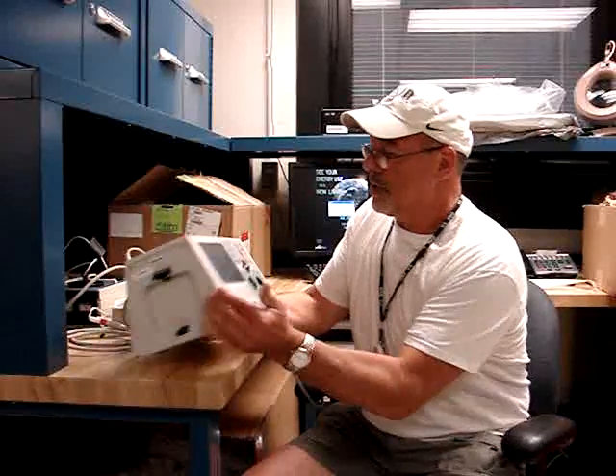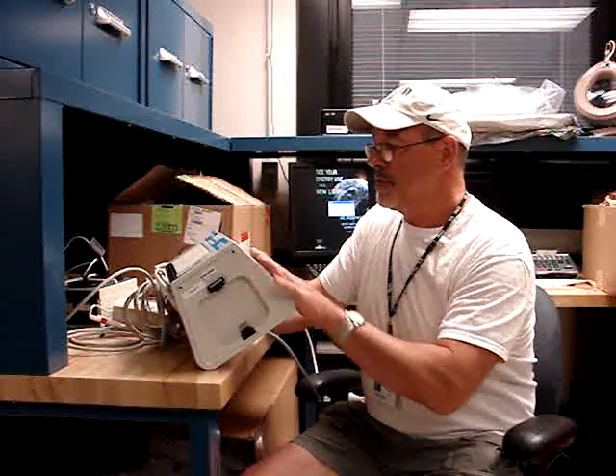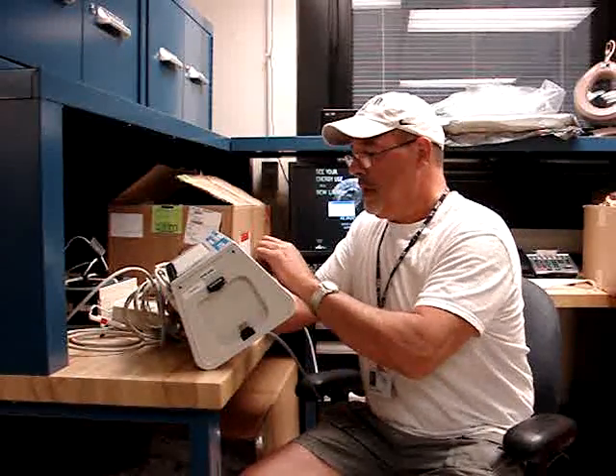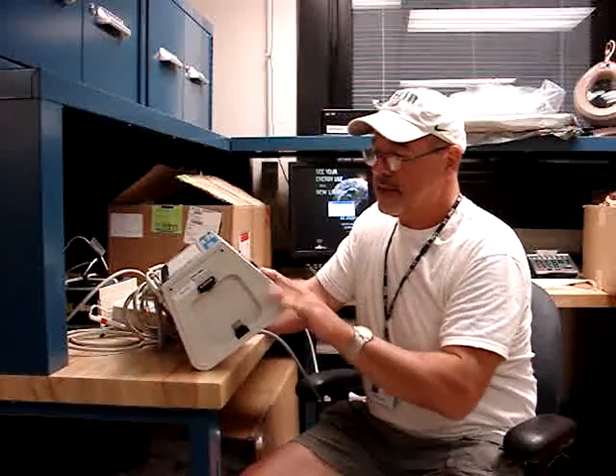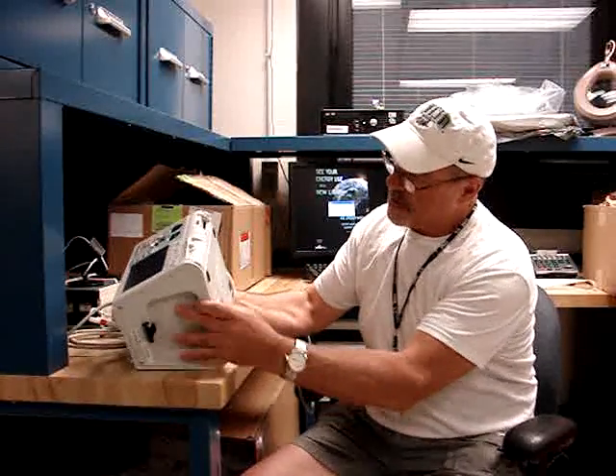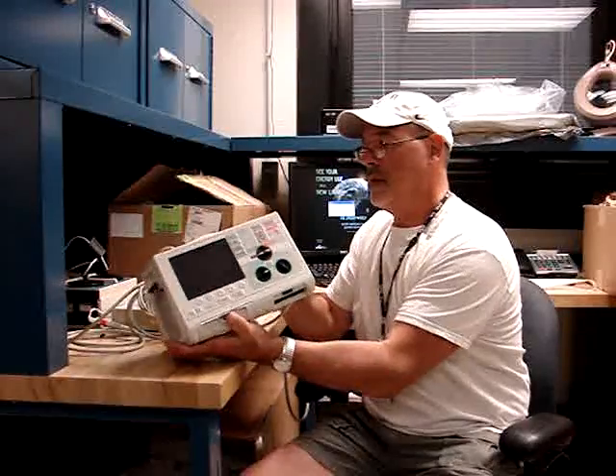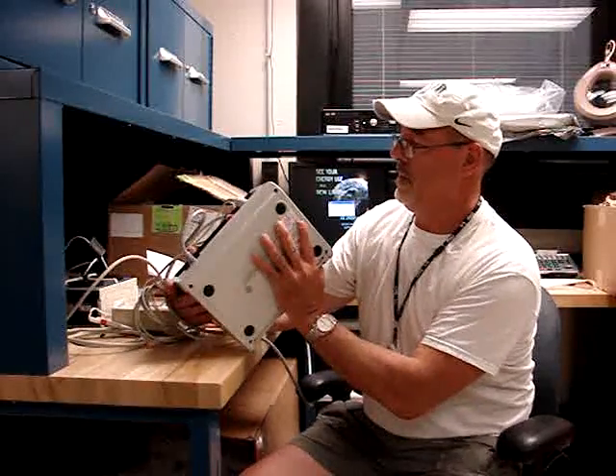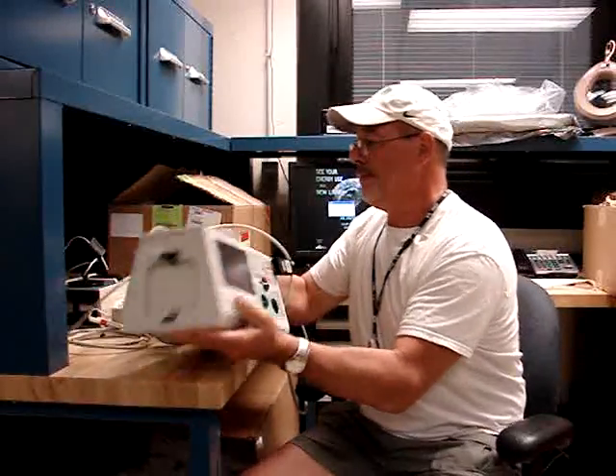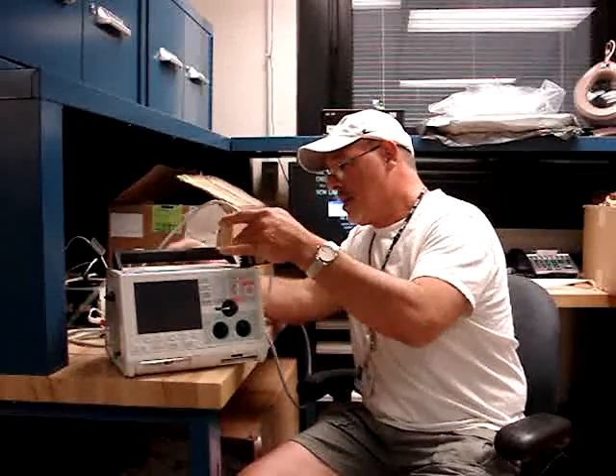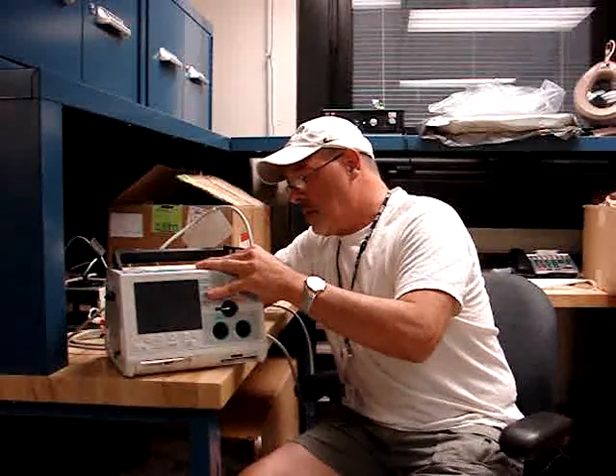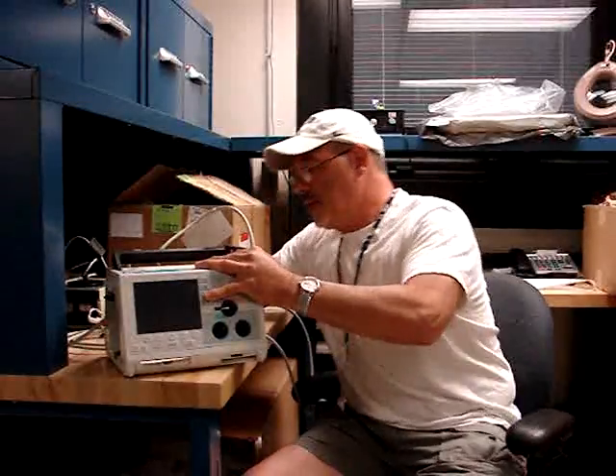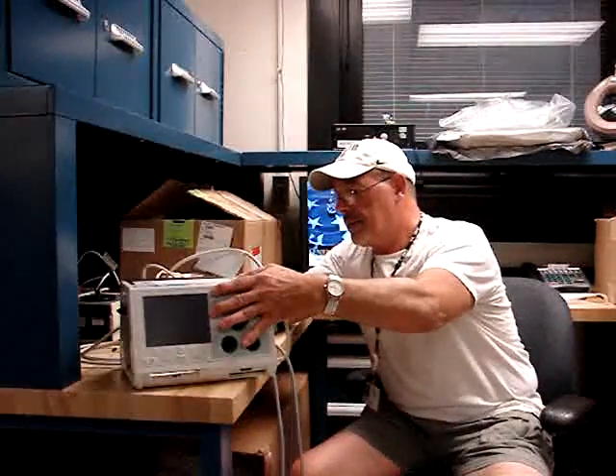So we will do a general look over, make sure there's no scratches on the screen, all the buttons are in place and set, no cracks on the outer exterior anywhere. Looks good. Okay, next thing we're going to check is our plug. Make sure our plug's not frayed, make sure it fits securely in. We're going to check the strain relief and it's secure.